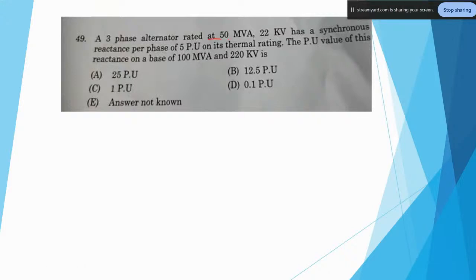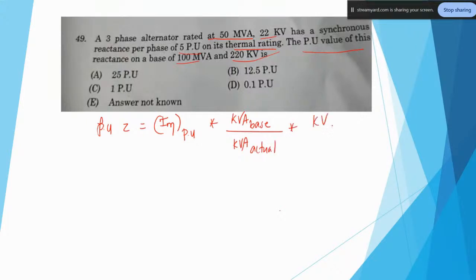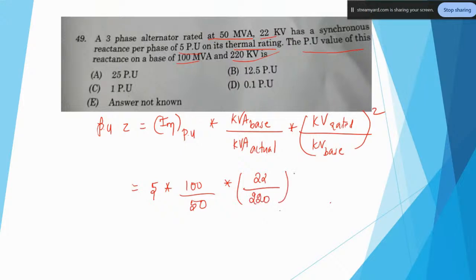49. A three-phase alternator rated at 50 MVA, 22 kV has a synchronous reactance per phase of 5 per unit on its thermal rating. The per unit value of this reactance on a different base, that is 100 MVA and 220 kV, is what? Per unit impedance equals impedance per unit into (kVA base divided by kVA actual) into (kV rated divided by kV base) the whole square. So 5 into (100 by 50) into (22 by 220) the whole square equals 0.1 per unit. Option D is the correct answer.